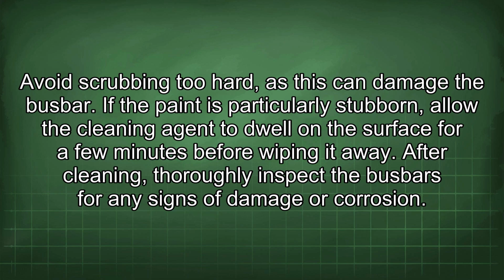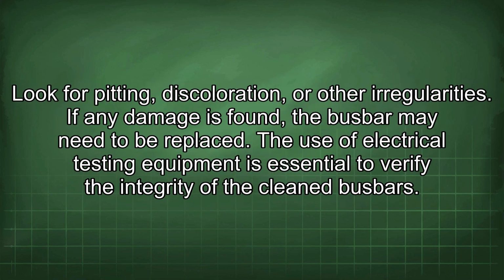If the paint is particularly stubborn, allow the cleaning agent to dwell on the surface for a few minutes before wiping it away. After cleaning, thoroughly inspect the busbars for any signs of damage or corrosion. Look for pitting, discoloration, or other irregularities. If any damage is found, the busbar may need to be replaced.